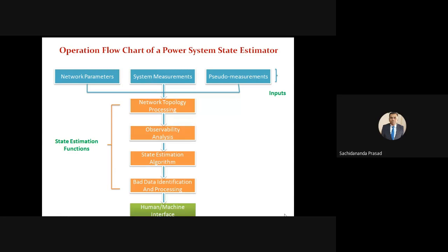Then observability analysis, because for the estimation we must keep a minimum number of measurements. Otherwise, if you provide insufficient measurements, the state estimation algorithm will not converge. So for convergence, we must need a sufficient number of measurements. If sufficient measuring devices are not available in the grid, we take the help of pseudo measurements, retrieving data from history, and using that as a measurement in the system.